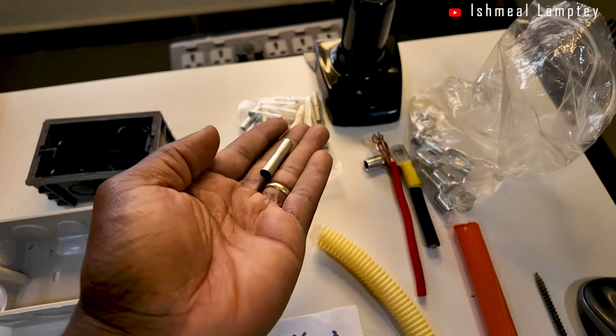Now, this also comes in different sizes. This is 16mm, there's 35mm, there are different sizes, smaller sizes as well for smaller cable terminations, among others. So in a nutshell, these are some basic things that you can pay attention to, especially the size of cables being used for the right type of work. And also, one thing I need to point out is that it is very bad to combine different sizes of cables on a circuit. So imagine an example where you have 4mm coming, then you connect 2.5mm to that cable coming to the socket. No, that is not professional.